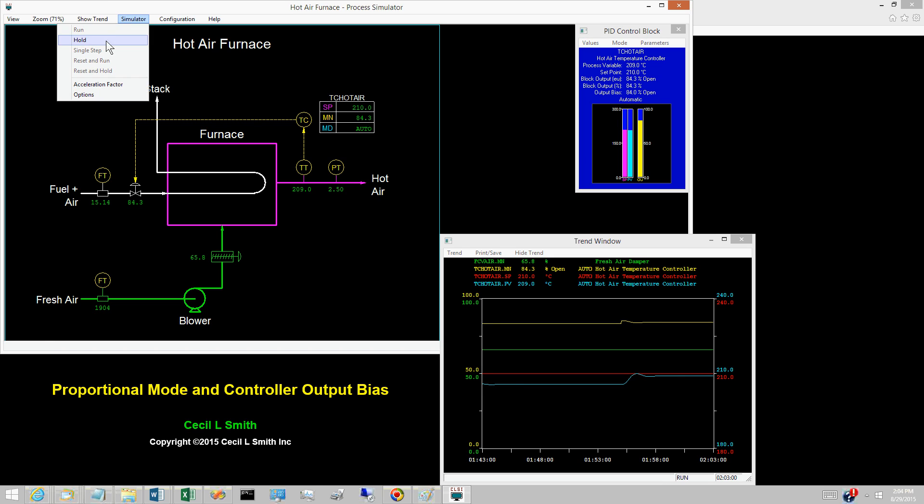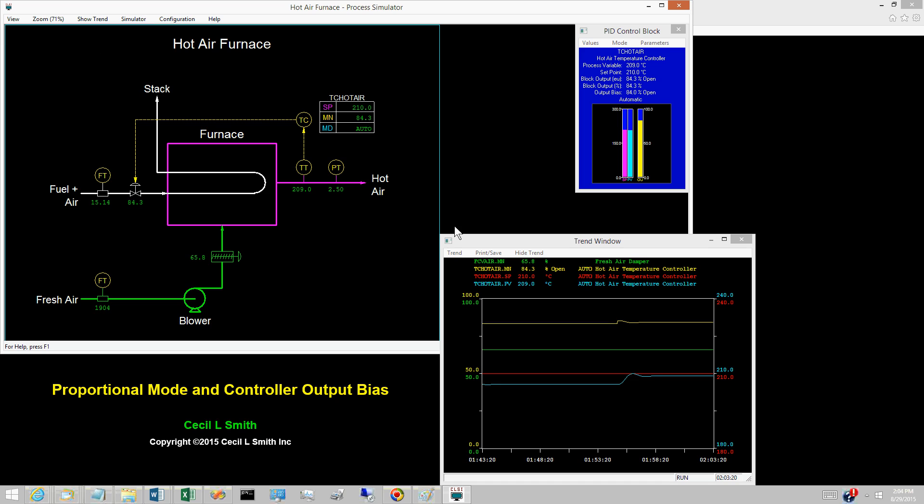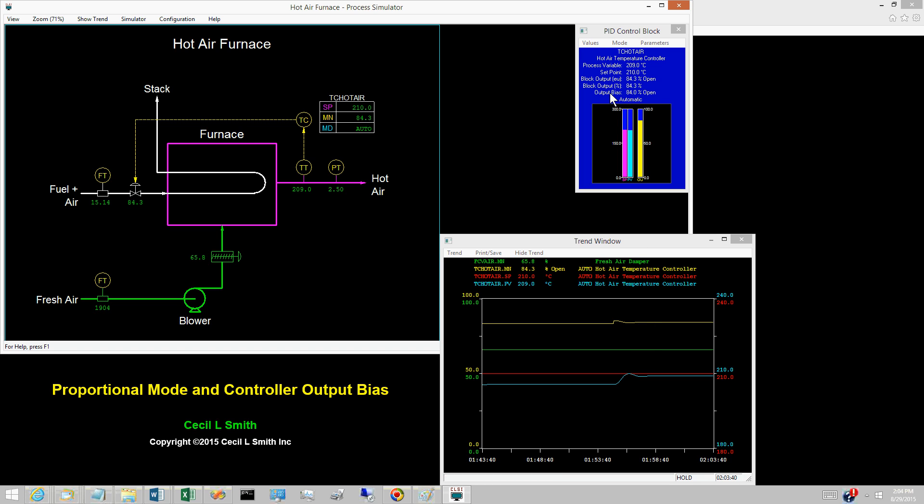Place the simulator in hold. Rarely do today's process operators know anything about Manual Reset and adjusting the controller output bias. Such requirements became obsolete with the introduction of the integral mode, often called automatic reset or just reset. The integral mode adjusts the controller output bias until the PV lines out at the set point.